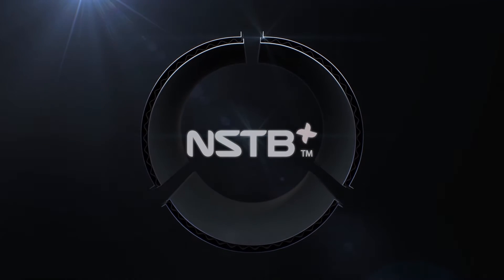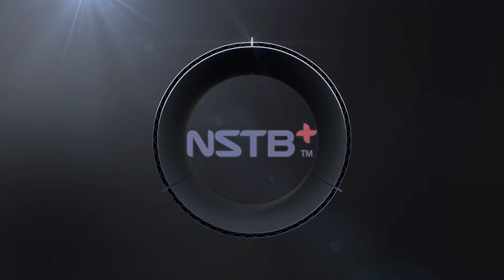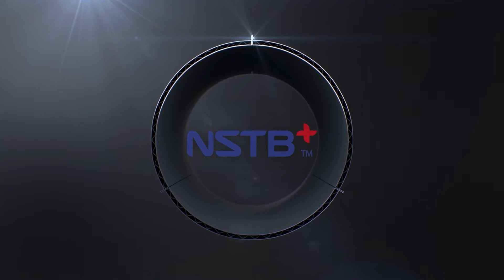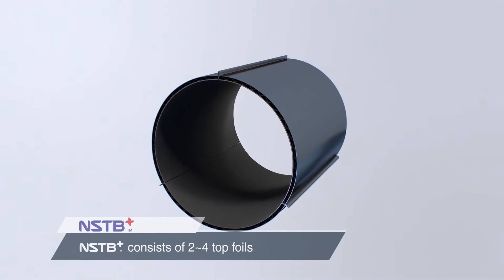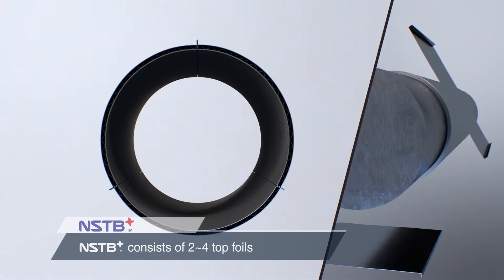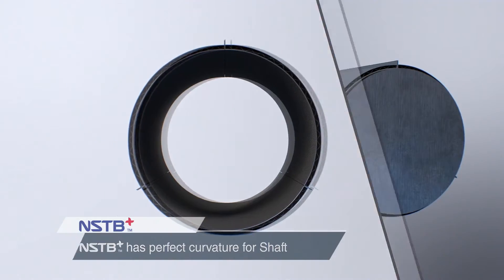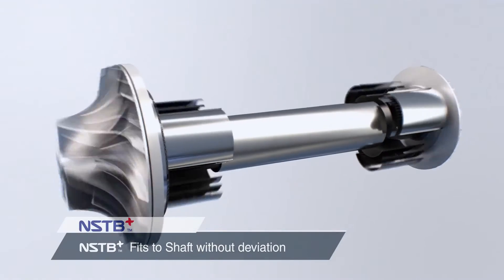NSTB+ is Turbomax's special airfoil bearing that offers enhanced durability and stability by structurally upgrading NSTB. NSTB+ consists of two to four topfoils, and each topfoil has an optimum curvature that fits to the shaft without any deviation.